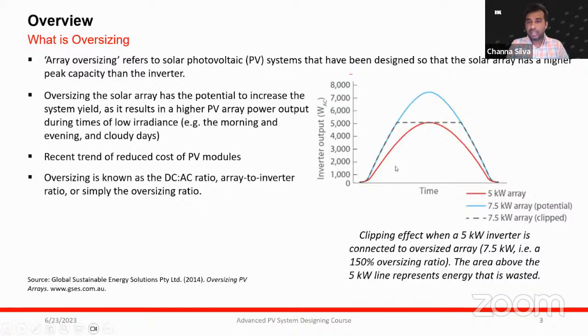Let's look at a graph. In this case we've taken a 5 kilowatt inverter with the first red color graph connected to a 5 kilowatt array, so it's like matching array capacity to inverter capacity. But what oversizing exactly is, is connecting a much higher capacity rated power output from the PV array to a selected inverter. In this example, the array is oversized by 50%, so in normal terms we say 150% oversizing - connecting a 7.5 array to a 5 kilowatt inverter. So what happens?